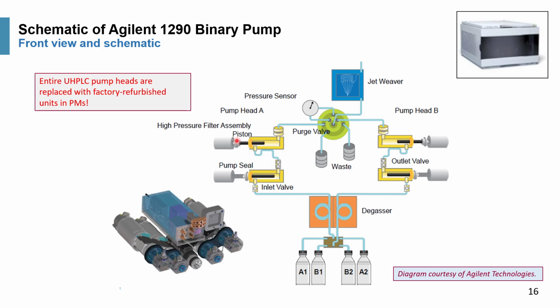The 1290 also uses an automated purge valve, so you don't have to do it manually. And actually, you have sufficient power so that you do not need to dry prime it. Actually, you can pump it right in the dry state. The mixing is done by a high-tech mixer called a jet weaver, which has 2 sides. For a high throughput screening type of sample, you can use the 35 microliter side. But for most other applications, for most pharmaceutical labs, you should use the 100 microliter, the larger jet weaver mixer.